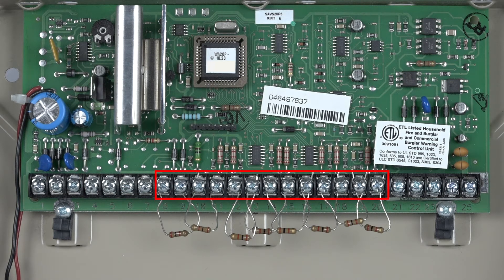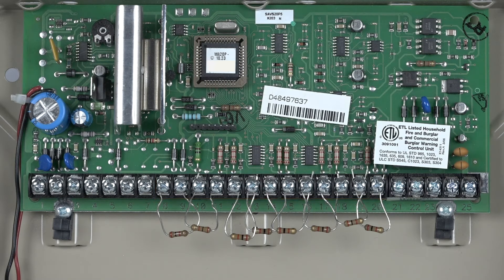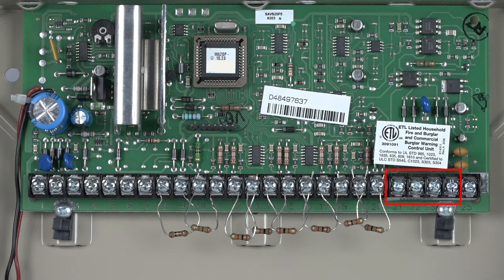Terminals 8 through 20 are your zone terminals. It is recommended to strap out these zones with 2K resistors if you are not using the zones since these have program values by default. Terminals 21 through 24 are for a phone line connection and Terminal 25 is an earth ground.